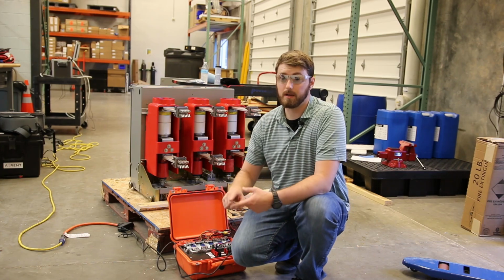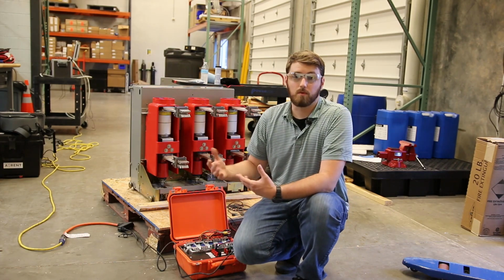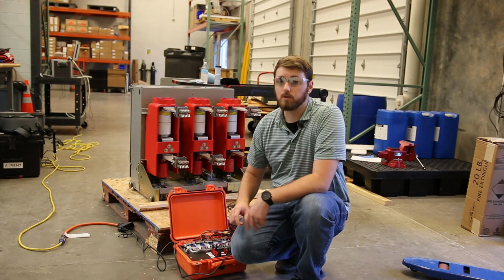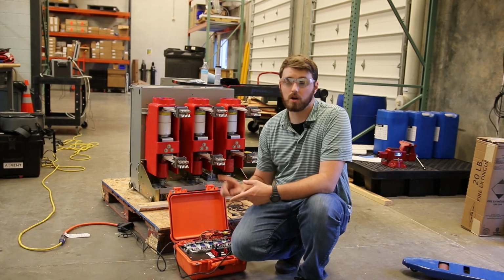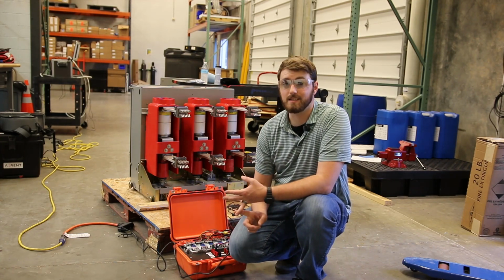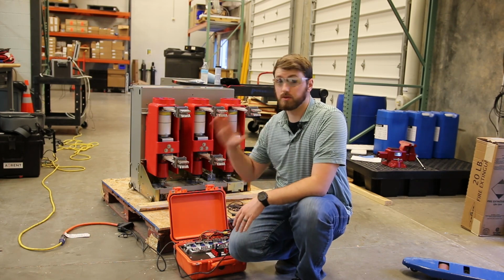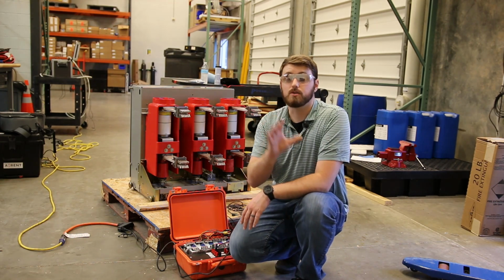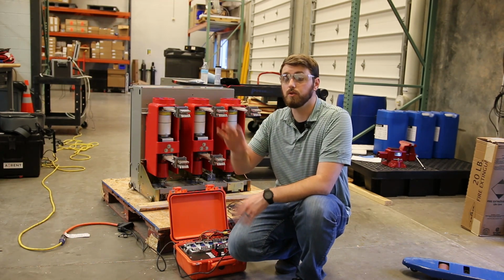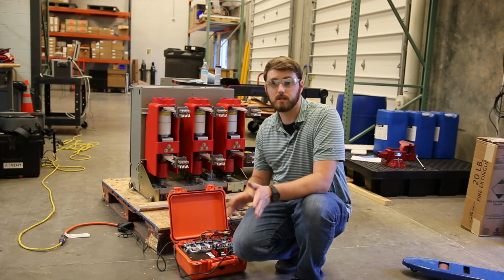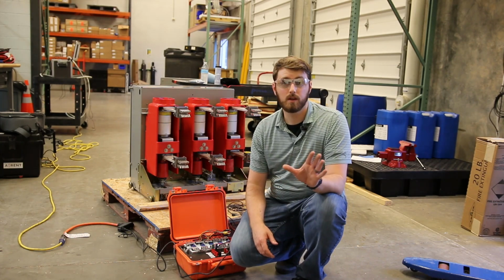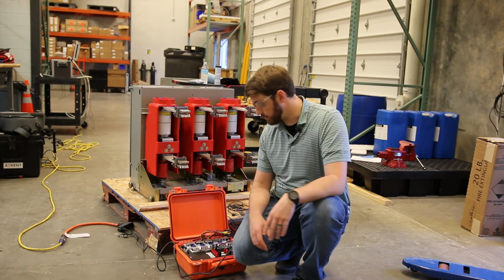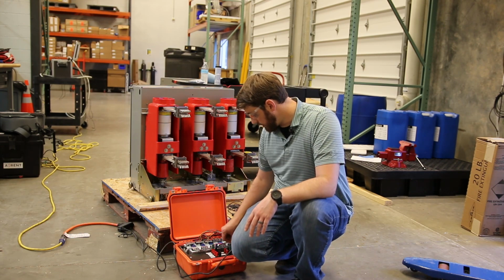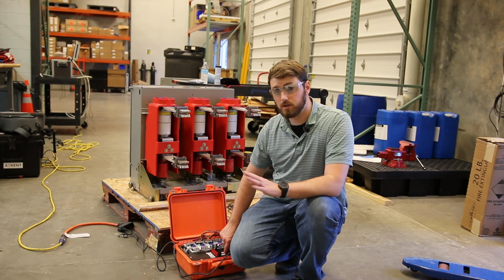That's going to be different depending on the breaker. Some run on AC charging motors and DC controls. Some have AC charge and close, but a DC trip coil. So just verify what you actually need for your breaker. This is going to be different for each of them. Again, read the manual for your breaker and it'll have all this information in it. So we're going to turn this on and see what happens. It should charge and do nothing else.